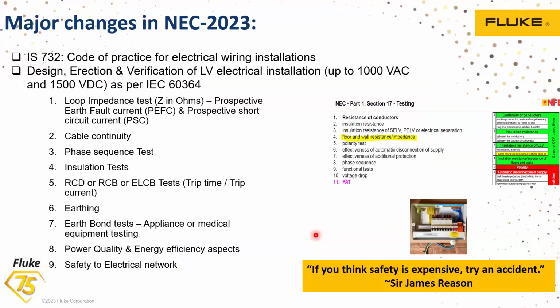Now, what are the major changes from the NEC point of view? NEC is talking about electrical safety, no doubt about it. Under that, as per the Indian Standard Code of Practice for Electrical Wiring Installations, they are talking about the design, erection and verification of the low voltage side, which is rated up to 1000 volt for the AC side, and 1500 volt for the DC side. This 1500 volt, we are talking about solar installations. The 1000 volt AC side is within your facility.